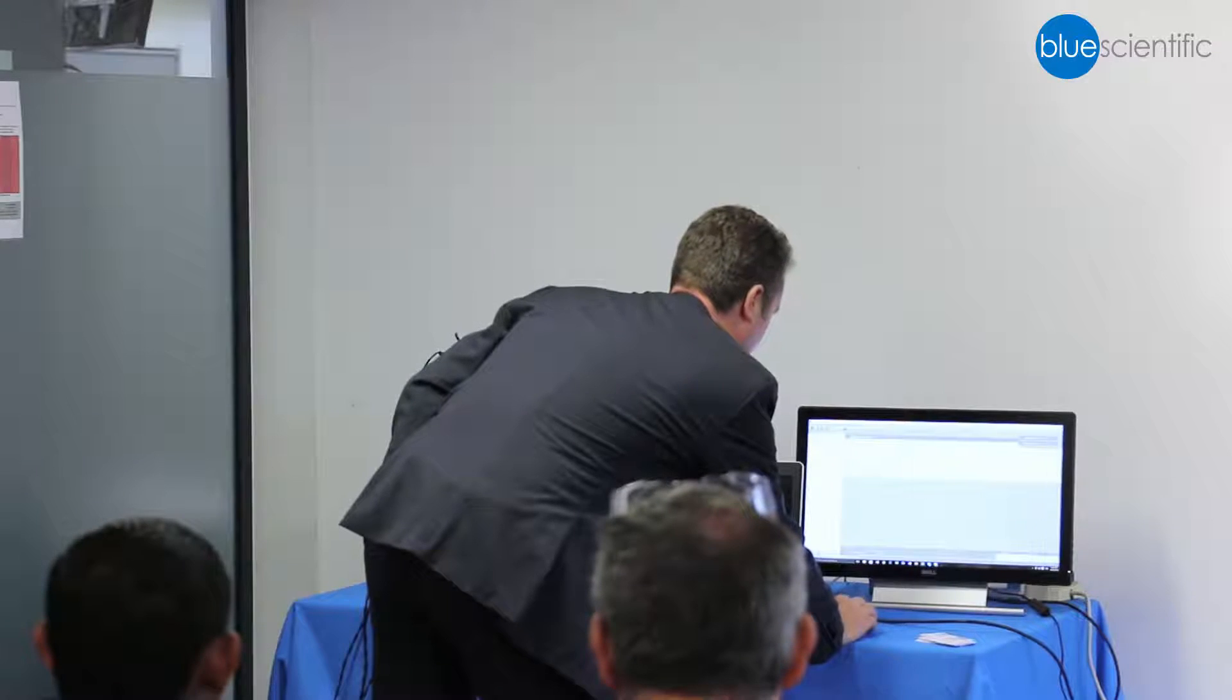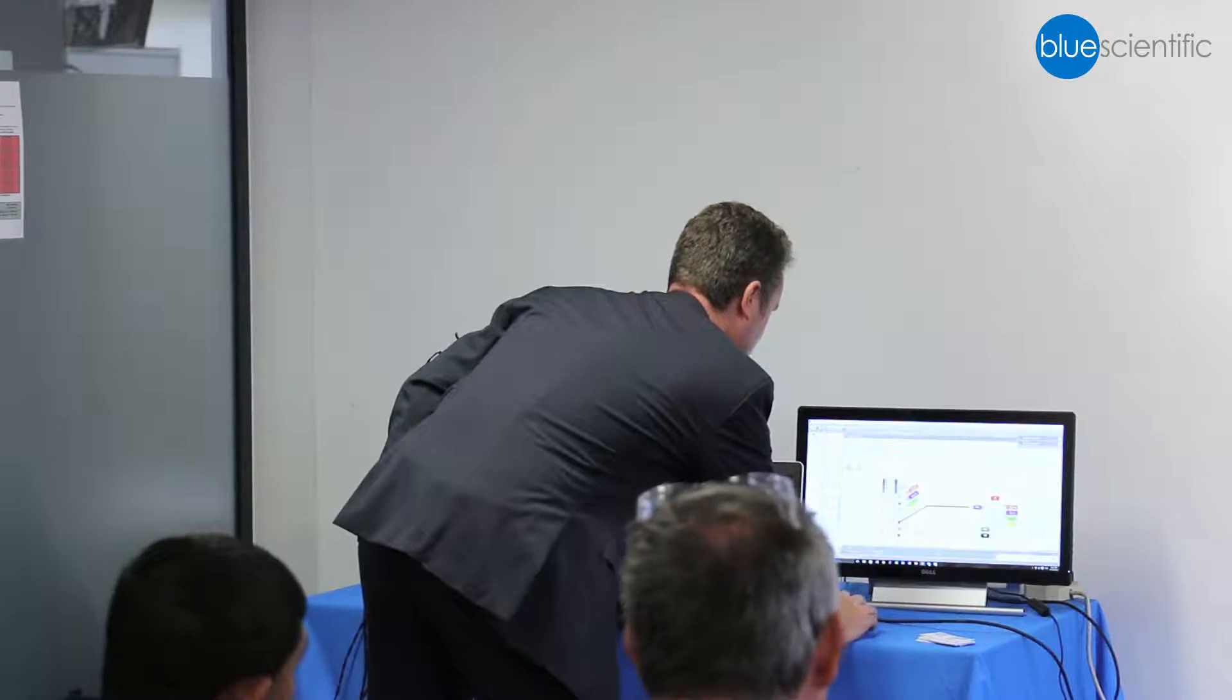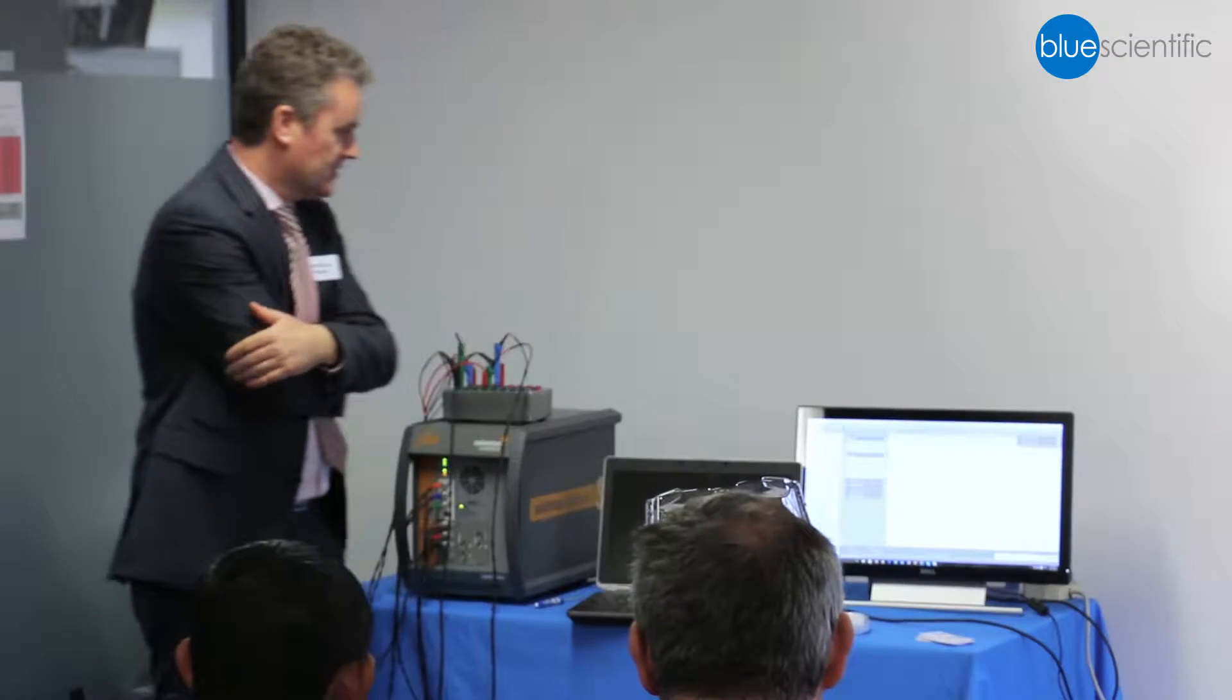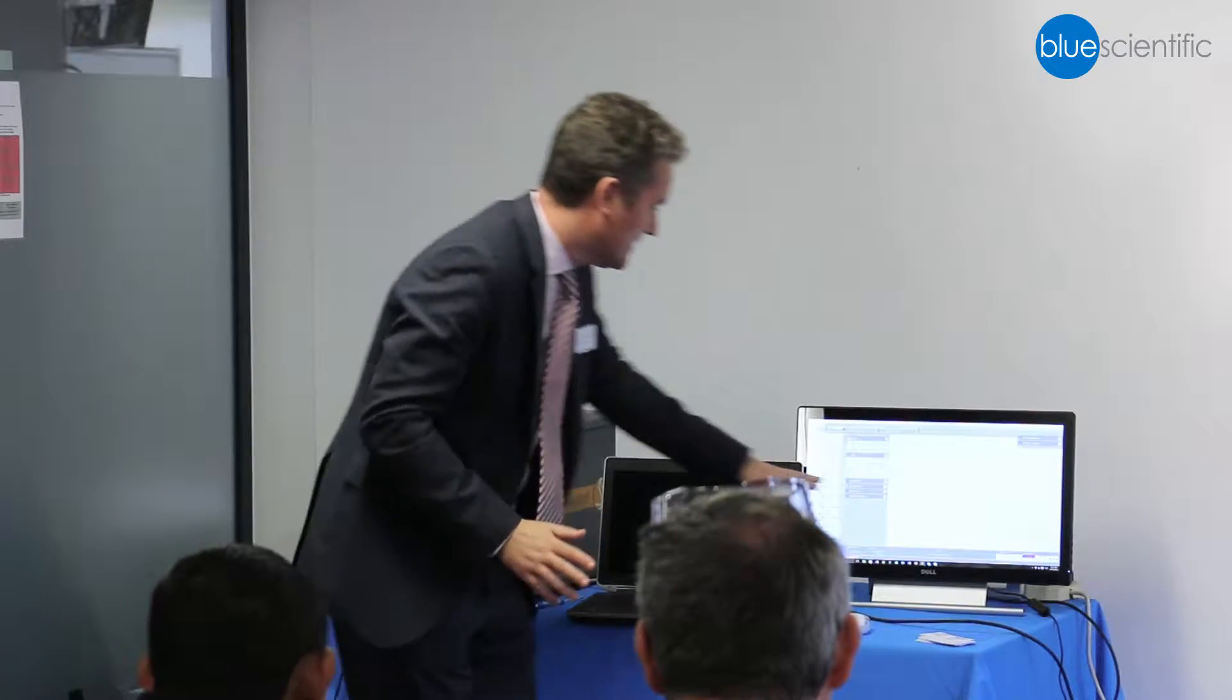It's going to make a measurement. I've already set up a project, so I'm just going to run that, and I'll explain what it's doing as we go through. So, I'm just going to measure the impedance of the stack. There's two batteries connected in series in this case. And the first thing I'm going to say is, you can't see the numbers, but I'll tell you the numbers.